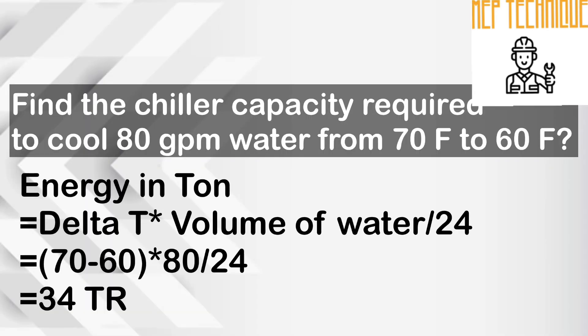Now we will calculate the chiller capacity. The question is: find the chiller capacity required to cool 80 GPM water from 70 degree Fahrenheit to 60 degree Fahrenheit. We apply the same formula. Our delta temperature will be the difference between 70 and 60, and the water volume is 80 GPM. The value is 34 TR.